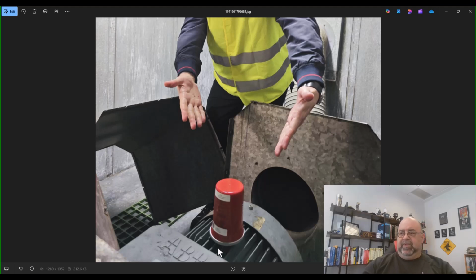It's being placed across two ribs, so it's not even directly connected. They're both at slight angles because this is a cooling rib. It's placed close to the connection box, well away from the bearings, and just glued. There was no removal of paint, nothing done to get proper metal contact. So with that paint contact, this is not going to detect early bearing issues, and it's not going to detect a lot of the conditions in the motor that start as high frequency stuff.